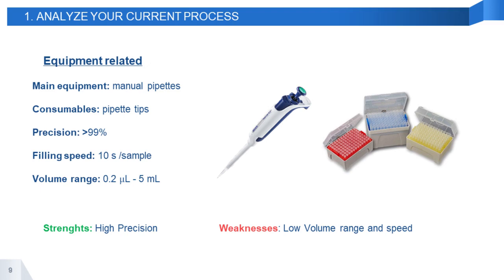The speed is disadvantaged by the methodology itself, because with these pipettes, you have to take a tip, moisten the tip with a reagent pool a couple of times, take the liquid and dispense it eventually. All that for each tube that needs to be filled in order to guarantee a proper dispensation and good precision. Besides, the volume range of these pipettes is very limited. Even the larger ones do not usually take more than 10 milliliters. The ones we had were able to dispense from 0.2 microliters to 5 milliliters. So we could now sort out those characteristics between strengths and weaknesses, being their high precision their best asset, and the low volume range and speed the main defects.